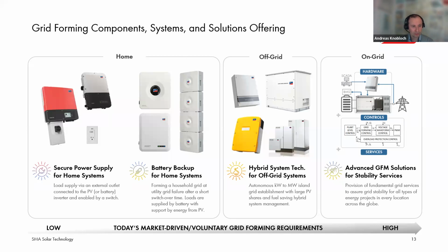If you would like to do it more secure, more firm, then we offer also some battery backup systems that are capable to form a household grid at utility grid failure after a short switch over time. You might have a manual switch where you switch to this operation manually, or it might also happen automatically depending on the system extent. And here the loads are supplied by the battery with the support by energy from the PV.